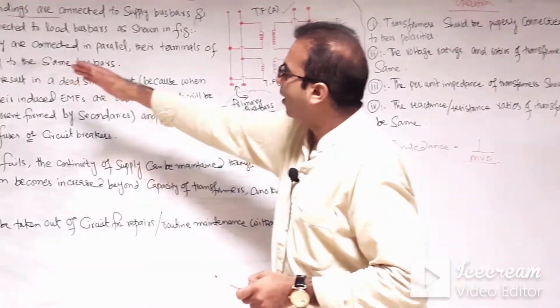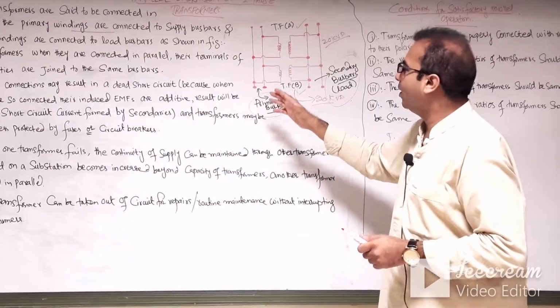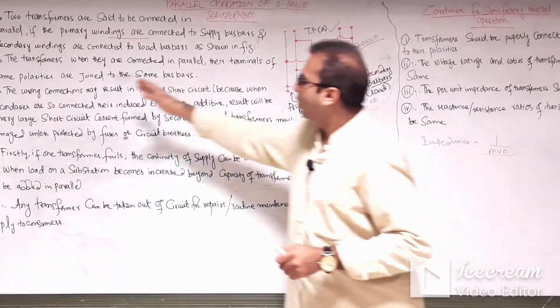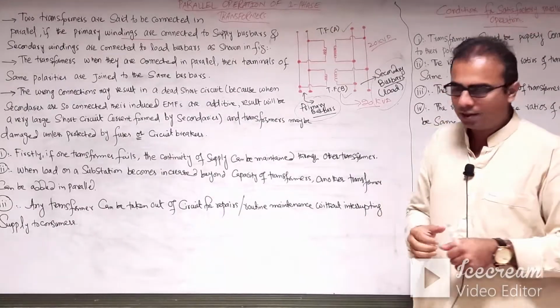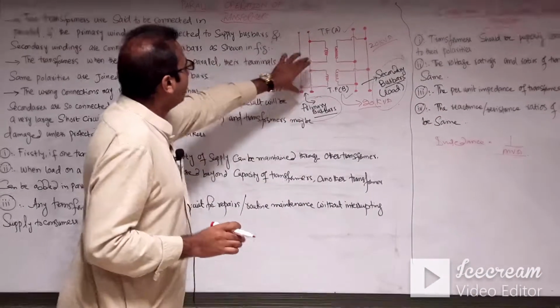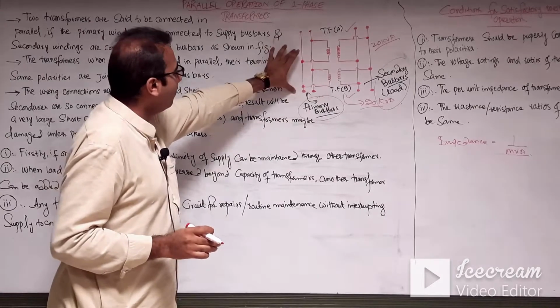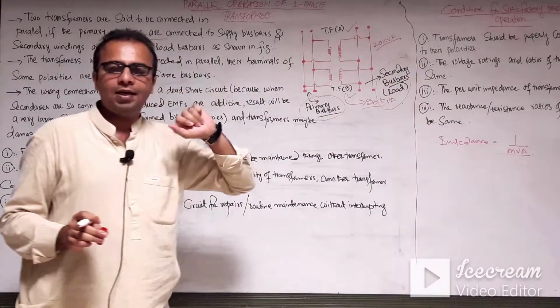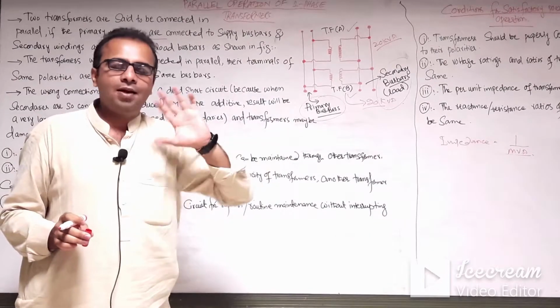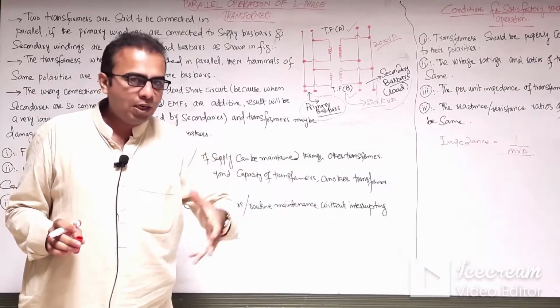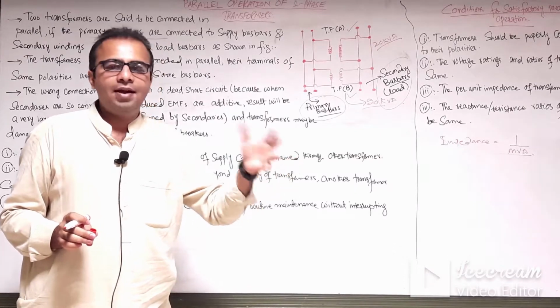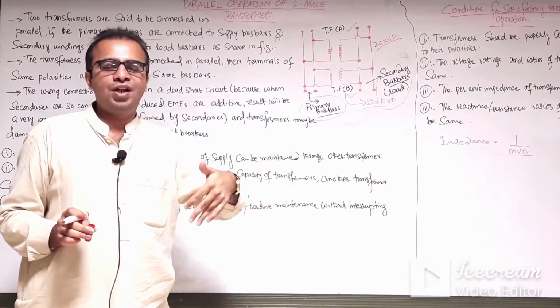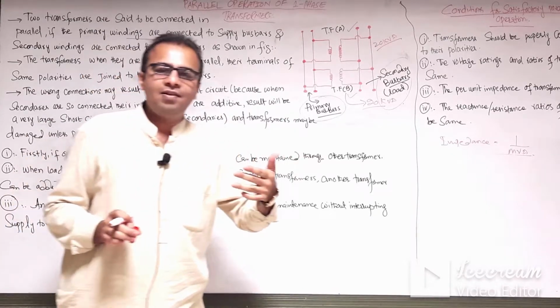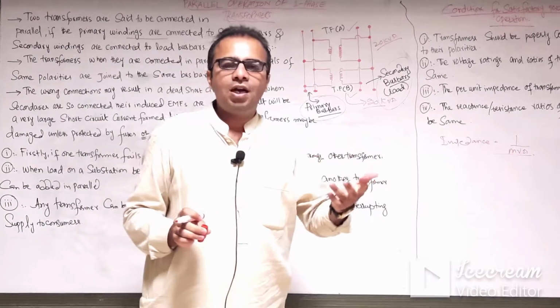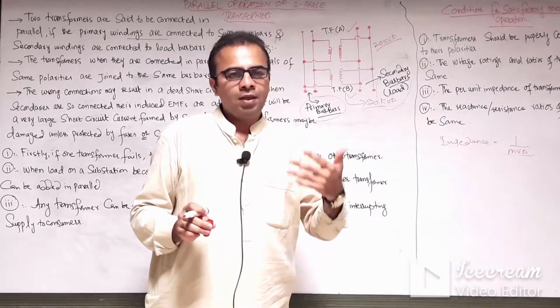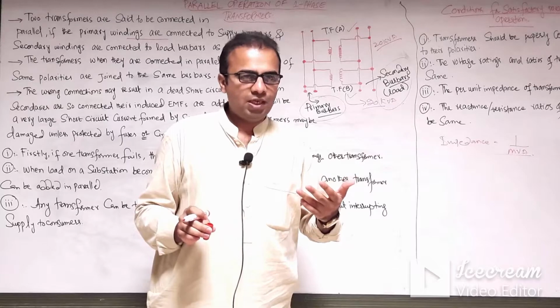Now when the transformers are connected in parallel, their terminals of the same polarities are joined to the same bus bars. Here the primary windings of the transformers are connected with the primary bus bars and the secondary windings of the transformers are connected with the load bus bars. So both transformers are connected in the same polarities. These polarities, additive and subtractive, or same polarities or opposite polarities, I have described in my previous lecture. You can find the polarity testing of the transformer in the playlist of my YouTube channel.